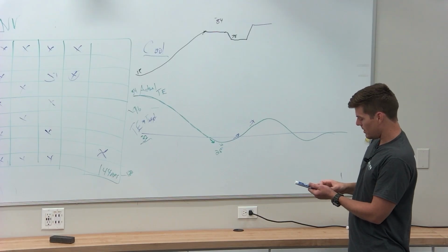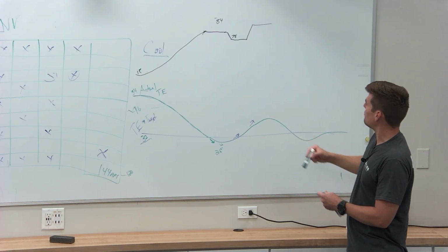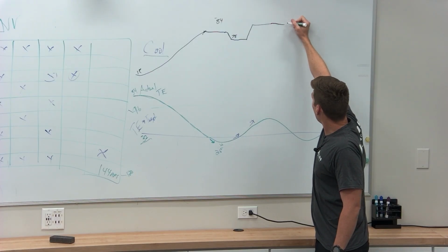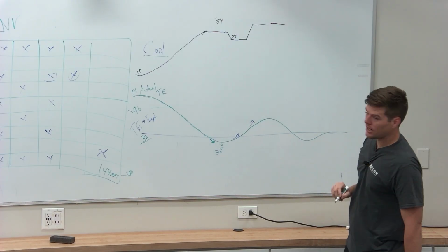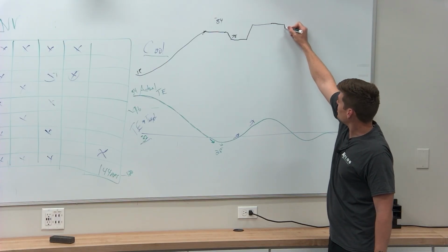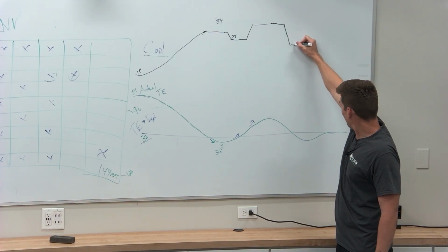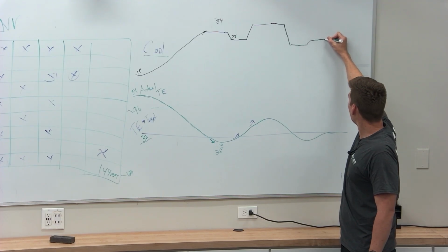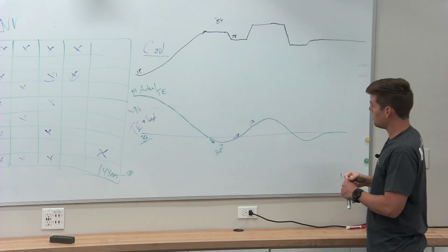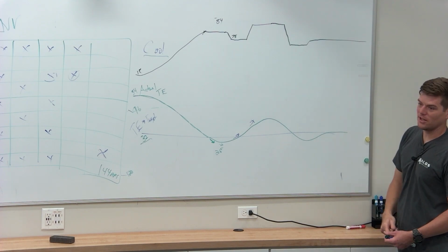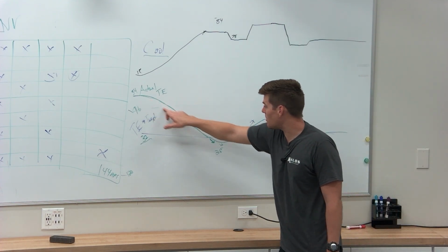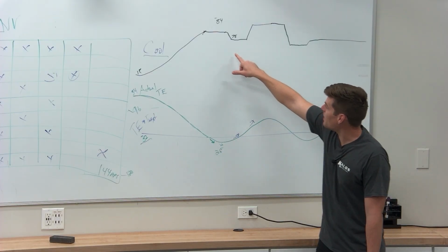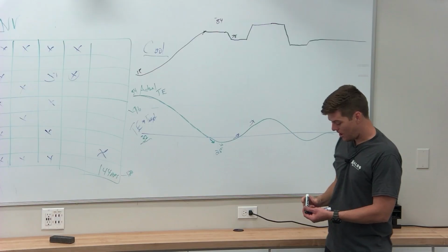And what you're going to find is then, okay, so then it starts to fall at this speed. It goes and it goes and it goes. And then you're going to find, oh no, we went past our line again. And so then it slows down. And then it goes and it realizes it's too slow. And then it goes up a little bit more. And then it levels out, right? This is what Service Checker data looks like. We can easily populate this number here and see how it dips on this line here. We can easily populate compressor speeds and see how they correlate to each other.